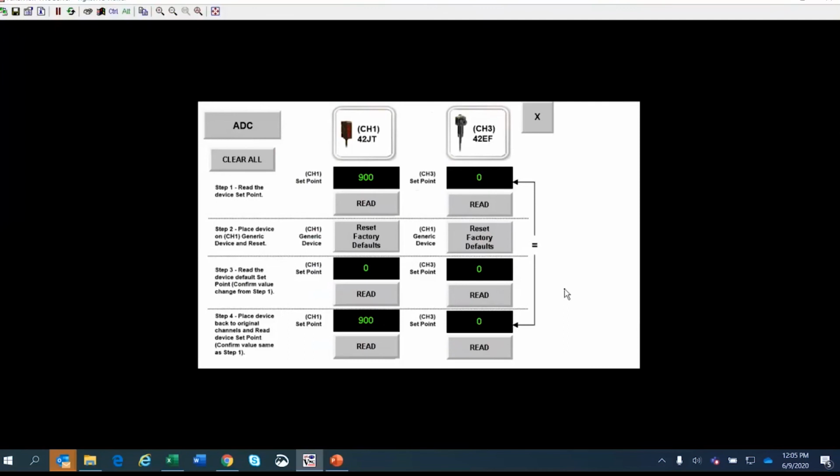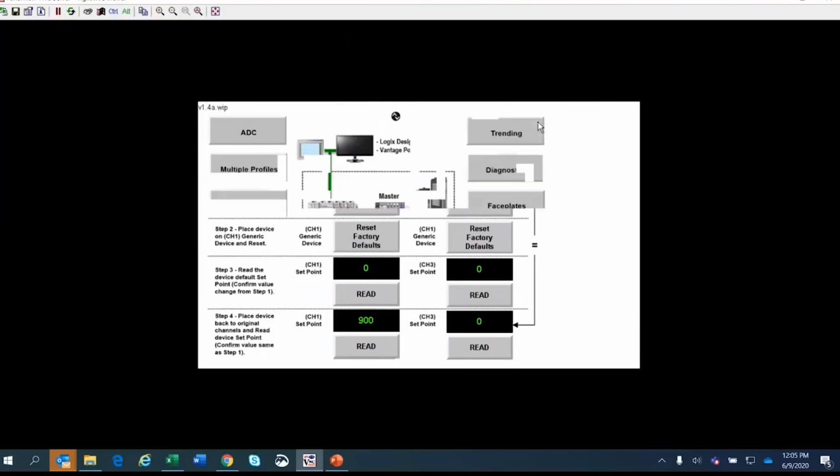On the right side sensors, we have a potentiometer. So when we were redesigning this, we designed it in a manner that you can actually set the sensor with the potentiometer, and store that setting in the PLC as part of automatic device configuration. When a sensor is to be replaced, all you have to do is connect the new sensor, and you don't have to touch the potentiometer at all. You can actually disable the potentiometer also. A lot of the plants have this issue that when something goes wrong, people tamper with the potentiometer, and then you can't even find what the issue was. So you can make the potentiometers, the knobs on these sensors, tamper-proof as well with the IO-Link capabilities, the smarts which we have put in.